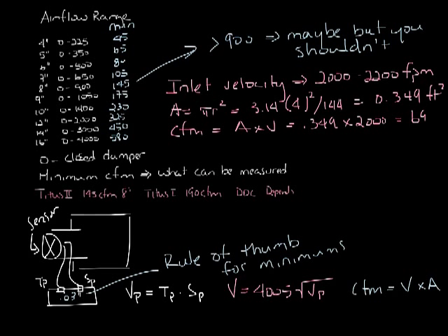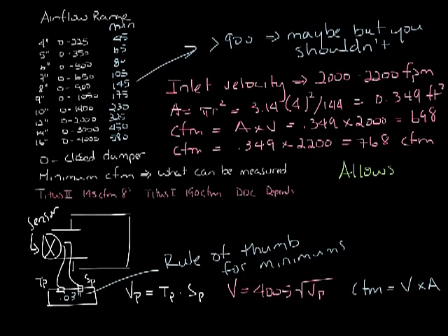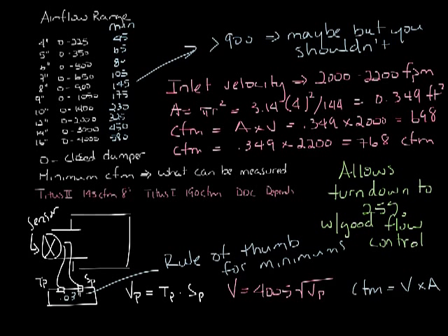From there you can calculate the CFM at 2,000 feet per minute as being 0.349 times 2,000, or 698 CFM. Or at 2,200 feet per minute, which comes out to 768 CFM. And if you select your inlet size so that you're near the 2,000 feet per minute range, you'll also be able to turn your box down to about 25% airflow, or 500 feet per minute, and still be able to maintain proper flow control.